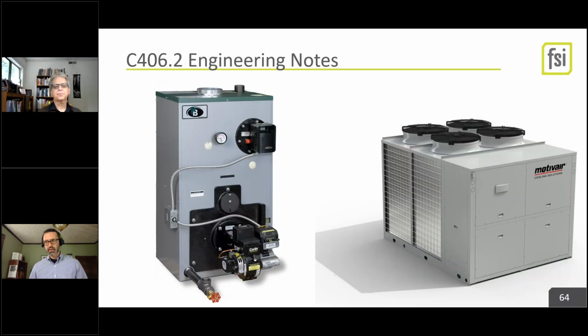I can say why. The question is, what's hard to get to 15%, or at least 5% minimum in capacity-weighted average? The answer is oil-fired boilers and steam boilers—large boilers have trouble getting over certain efficiencies. Even that 5% extra can be a challenge to find on the market. Some chillers have trouble meeting that 15% mark because their ratings are already pretty good relative to their theoretical maximum.